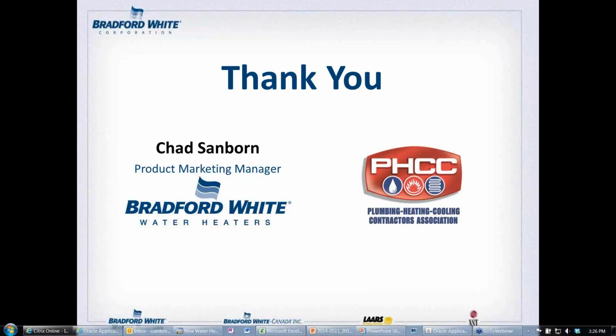Here's a good question. Will a 75-gallon tank with a 76,000 BTU per hour be affected by the new DOE rule? As it stands today, the answer to that question is no. Because it's above 75,000 BTU per hour, that product will not be affected. However, that's why I talked about what the DOE is proposing to redefine between residential and commercial. Once we get this final rule on that, which we expect to see any day, those products could and most likely will be brought into this criteria.